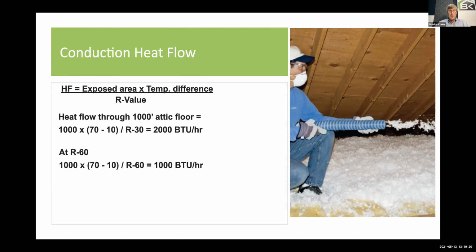Fair enough. Let's do R120. 1,000 times 60 divided by 120. Now my new heat flow will be 500 BTUs. So the first R30 I put in saved me 1,000 BTUs. Then I added another R60 and it only saved me 500 BTUs, the diminishing returns.